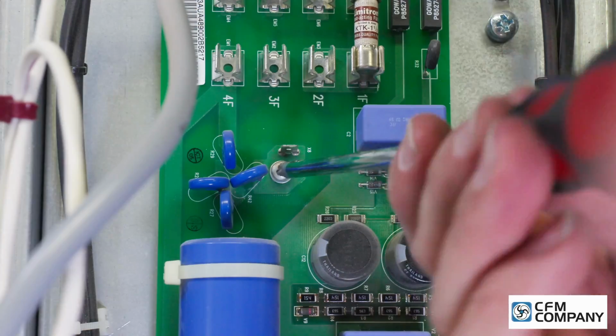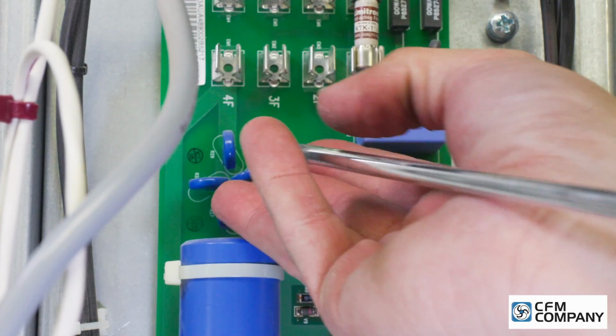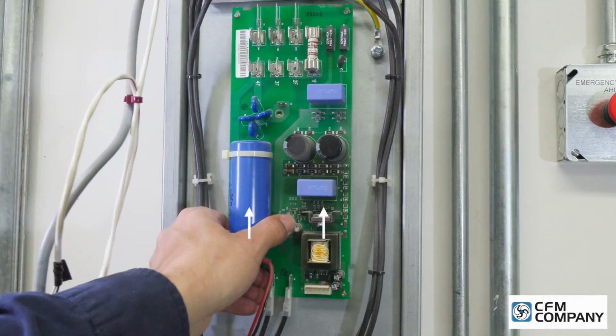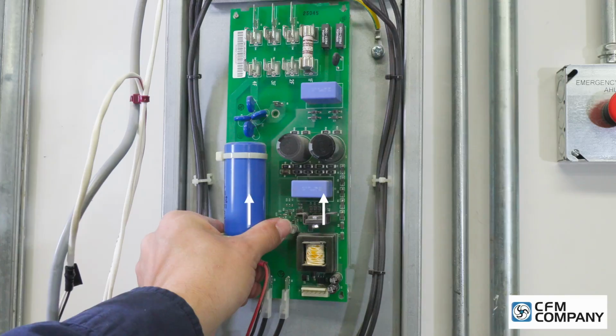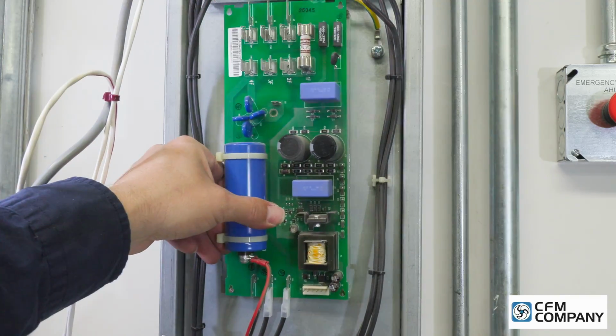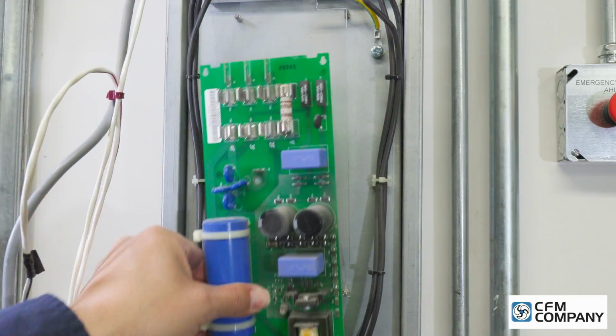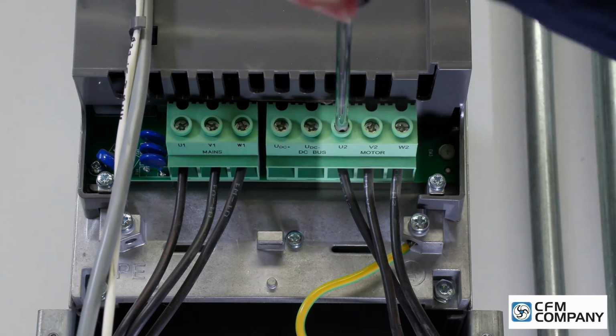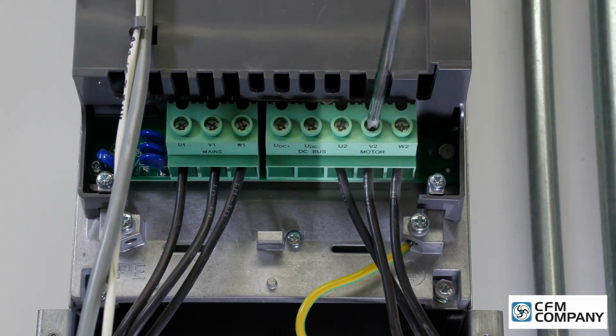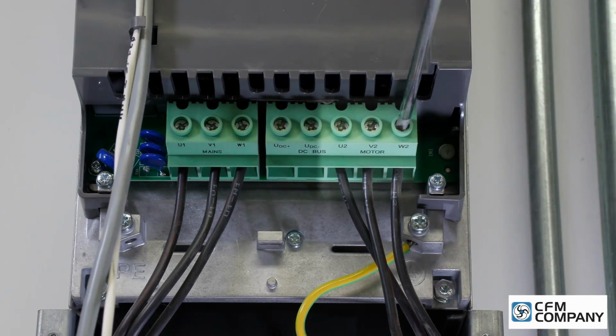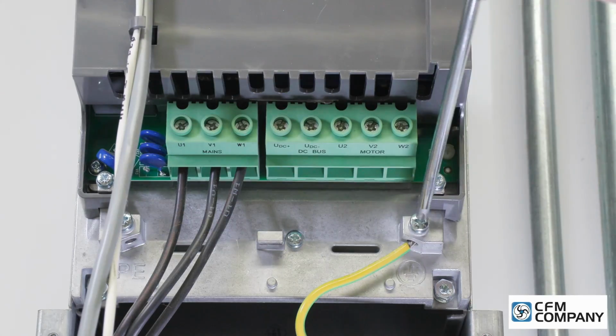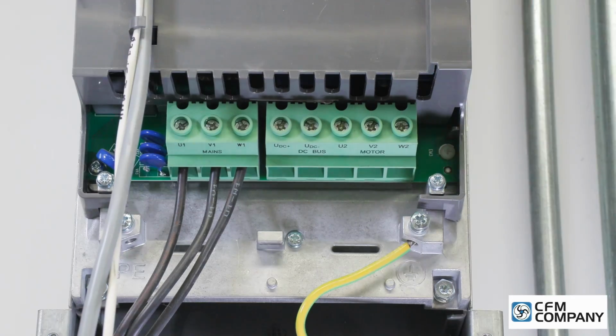Remove the center-mounted Torx mounting screw from the power board. Apply an upward pressure to the bypass power board. It should slide upward. Then remove the bypass power board from the slot pins. Next, remove the three-phase conductors from the VFD output terminals U2, V2, W2, labeled motor. Remove the ground conductor from the ground lug.